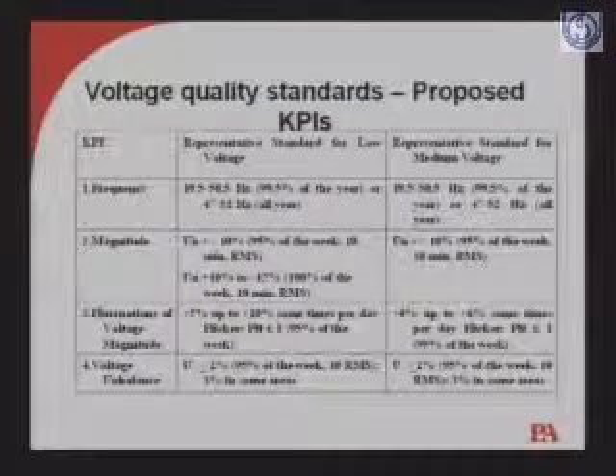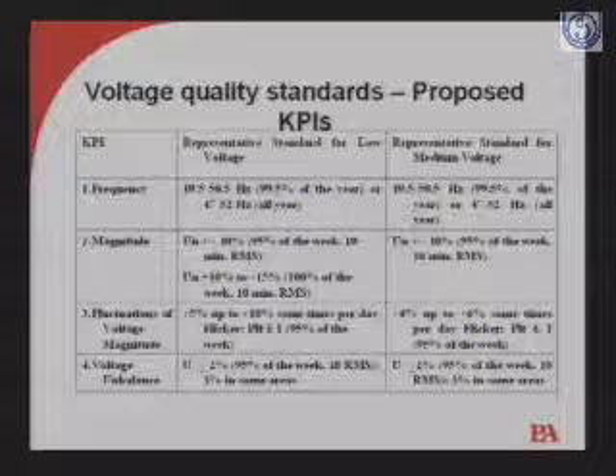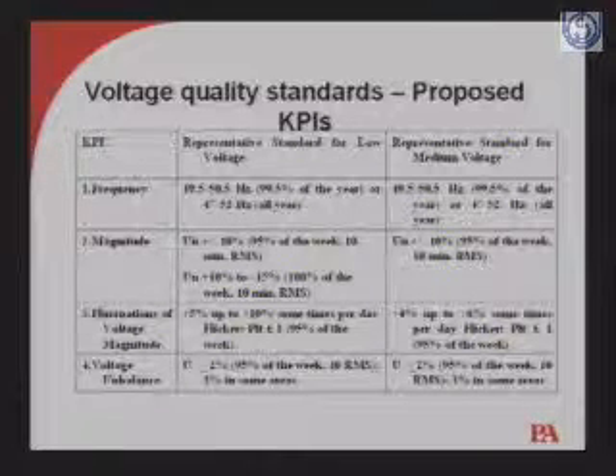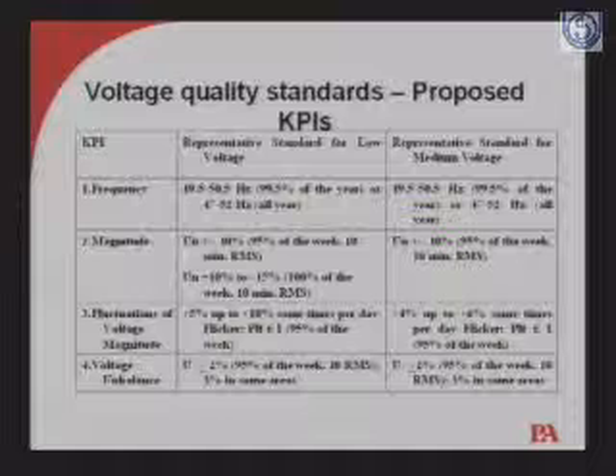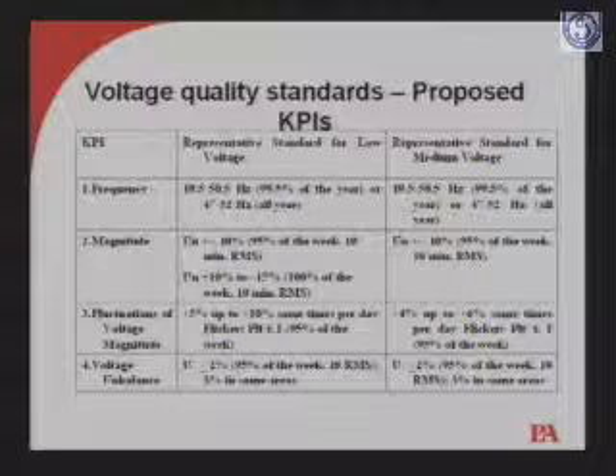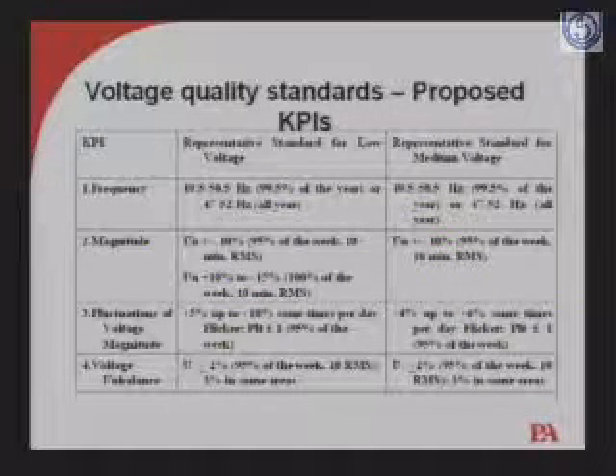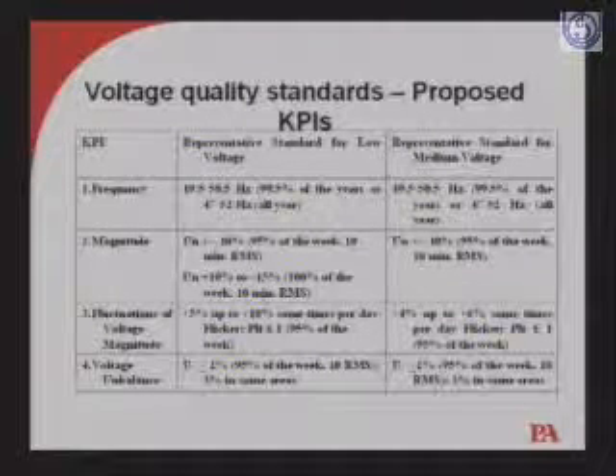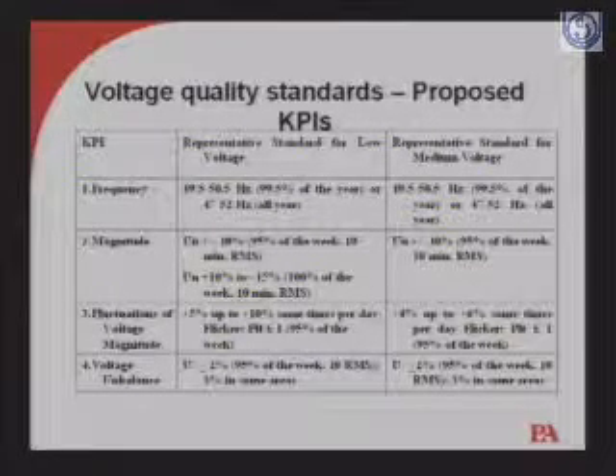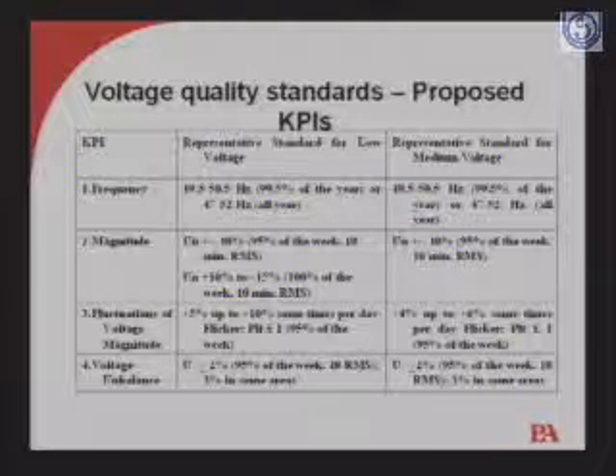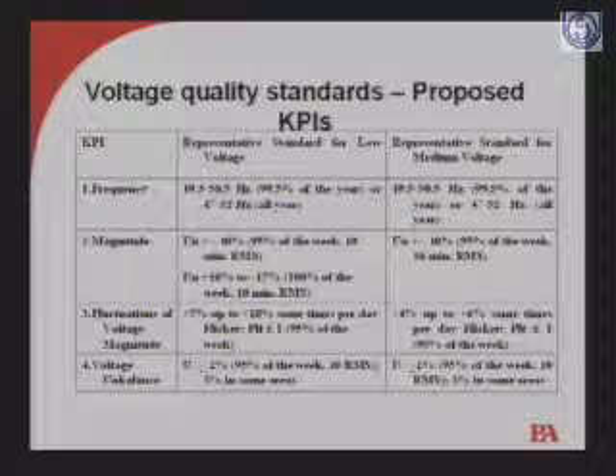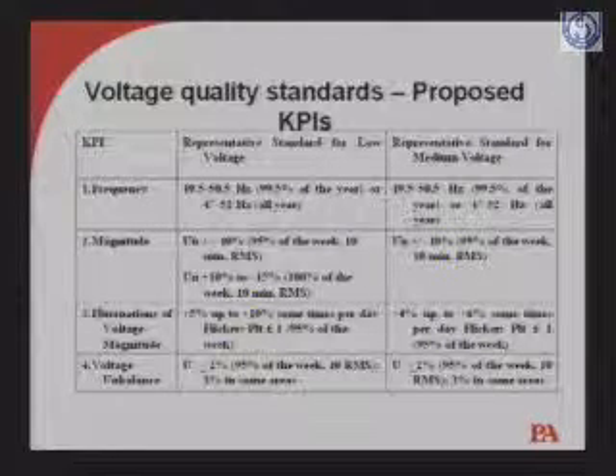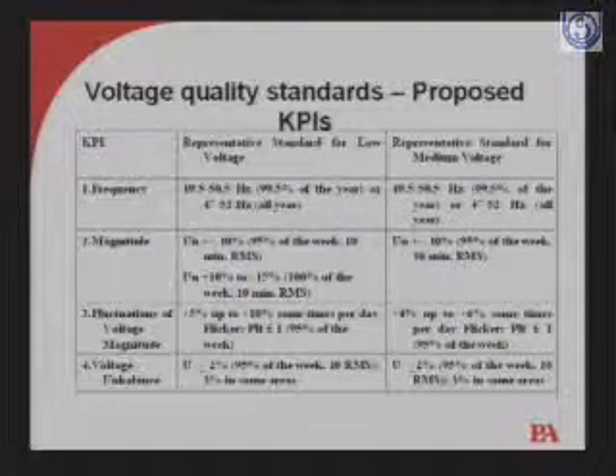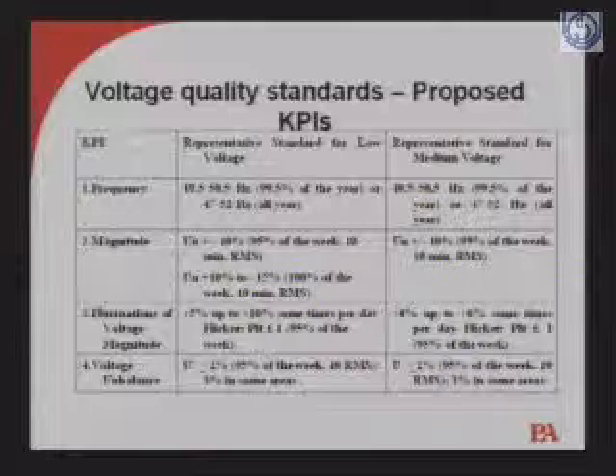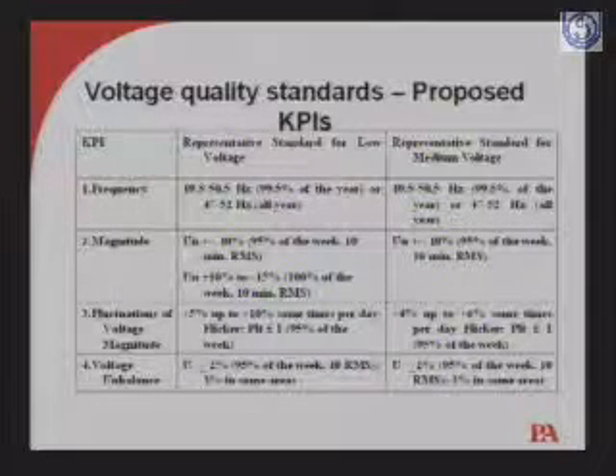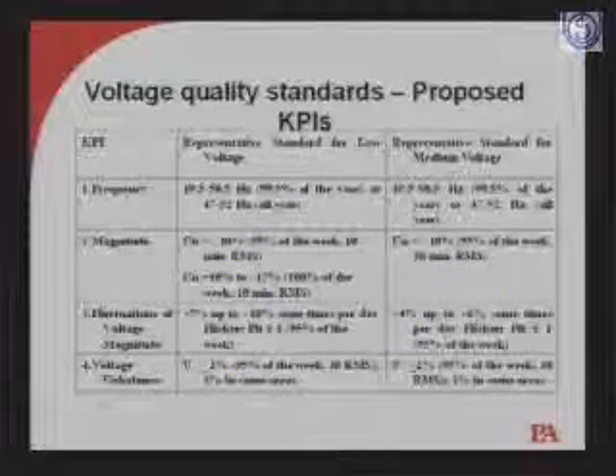Under DRUM we have suggested installation of voltage flicker meters, and it is in fact at present at the tender stage, so I cannot really elaborate now on the benefits which it may bring, but definitely in the near future we may see. Voltage unbalance means voltage in one phase with respect to the other phase, or phase voltage to neutral voltage of one phase, and similarly for the other phases. So it should not be more than 2% plus minus, or 3% in some cases, and the voltage should be constant for say 100% of the time, and at least for representative standard purposes we may have 95%.